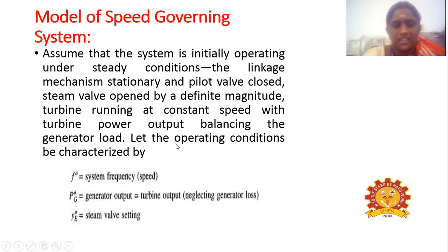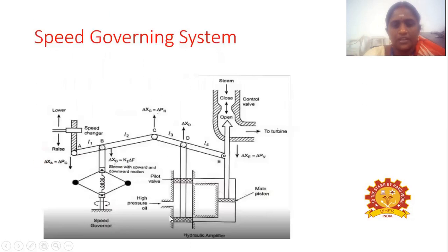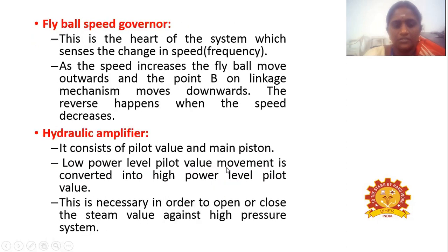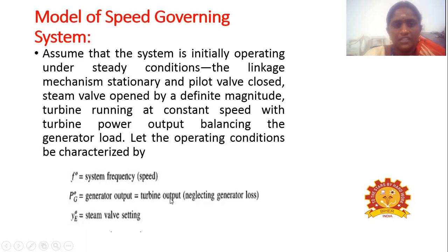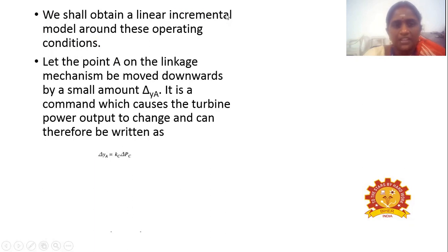See, in this case, let the operating conditions be characterized by F0 as system frequency, that is speed, PG0 as a generated output, that will be equal to turbine output, because here we are neglecting the generating losses. Then YE0 is the steam valve setting. So YE0 means that point E is connected to the main piston. So at the initial position you consider as YE0. So we shall attain a linear incremental model around these operating conditions.